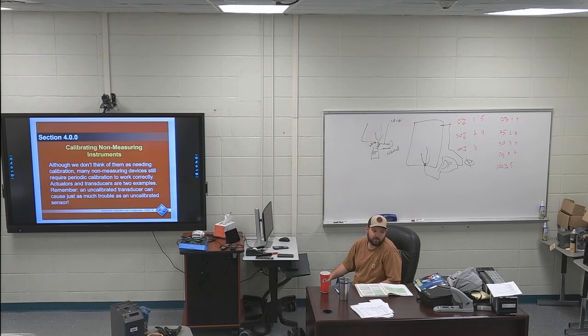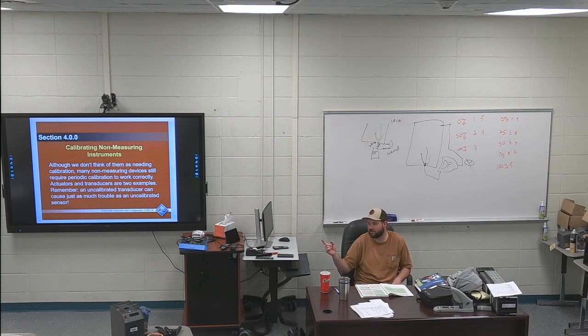So, what's the most common type of instrumentation transducer? I to P. Right? What to pressure? What does I stand for? Current to pressure. So for that control valve, I send in a 4 to 20 milliamp signal, and that corresponds to my 3 to 15 psi. So I'm inputting 4 to 20, outputting 3 to 15 psi. Does that make sense? I to P.